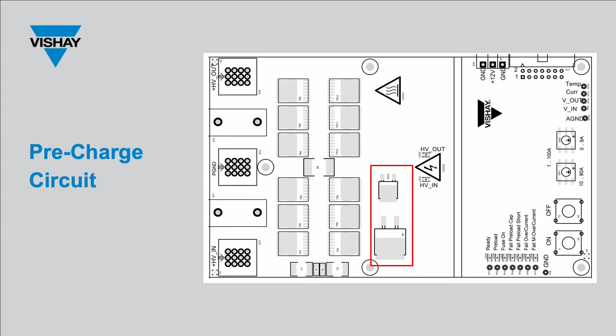As you can see from the layout, the main pre-charge components are located on the top side of the board near the 12 main power switches. The power resistor used for the pre-charge circuit in this design was a Vishay D2TO35 resistor. It's a thick film technology in a D² pack surface mount package and is designed for very high pulse load applications. The nominal power rating is 35 watts at a 25°C case temperature, but must be derated for higher operating temperatures. However, in this design, since the pre-charge circuit is basically a pulsed event, care must be taken to make sure the peak power rating of the resistor is not exceeded during that time.